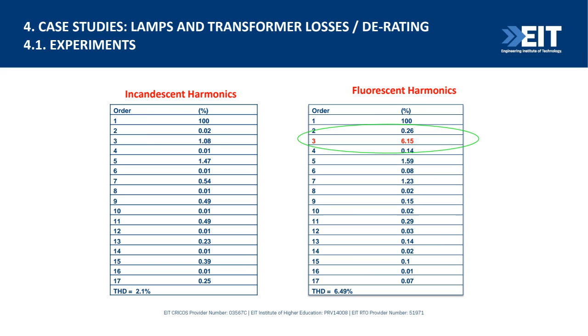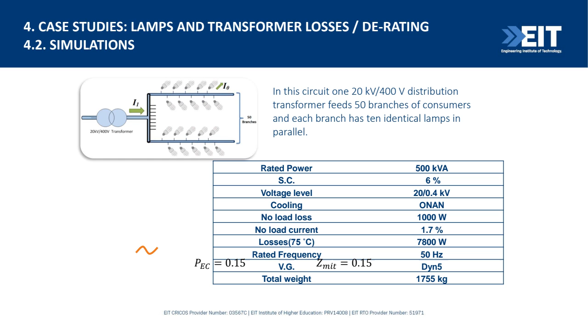Now we did a simulation as well, conducted in Matlab. We had a 500 kVA distribution transformer which converted 20 kV to 400 volts. It fed 50 branches of lamps, 10 identical lamps per branch, so about 500 lamps on the demand side. The rated power was 500 kVA, the short circuit impedance was 6%, the cooling was ONAN, the no load loss was 1000 watts, and the no load current was 1.7% of the nominal current. The rated frequency was 50 hertz, Z-mit was 0.15, and the vector group was DYN5.